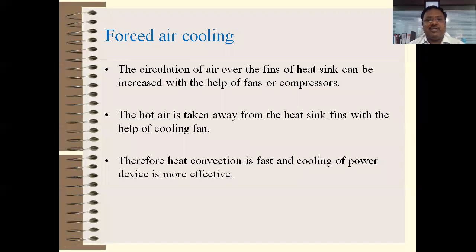So if the temperature of the heat sink is more, and with the help of natural convection it is not possible to dissipate the temperature, then in forced air cooling, a cooling fan is used to cool the heat sink. Sometimes exhaust fans are directly mounted on the heat sink fins so that they can take the hot air away from the heat sink and maintain the temperature of the heat sink. So this is basically called forced air cooling.